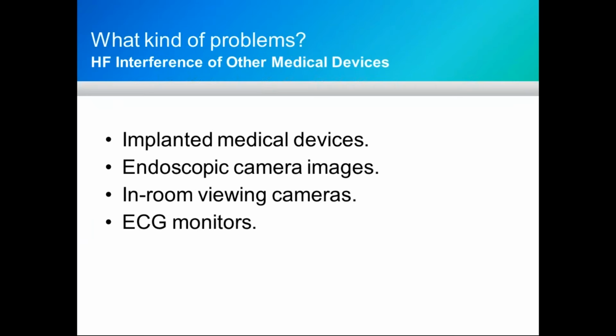What else can also be affected? Implanted medical devices, cameras, in-room viewing cameras, and ECG monitors. You've been in the room where the doctor is complaining that his monitor is getting some sort of interference, and that could be because of the electrosurgical unit. When you go in and test, that's the way you'll see if the electrosurgical unit is causing the monitor to have any kind of interference.